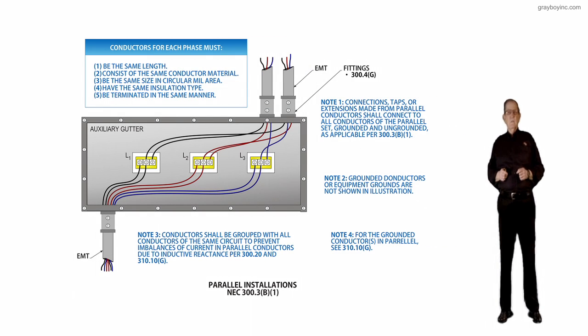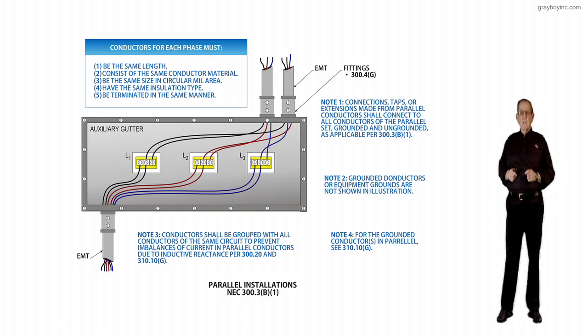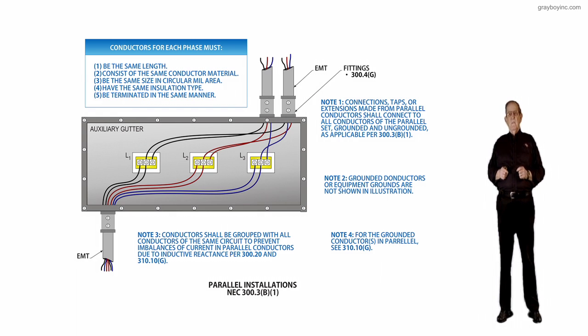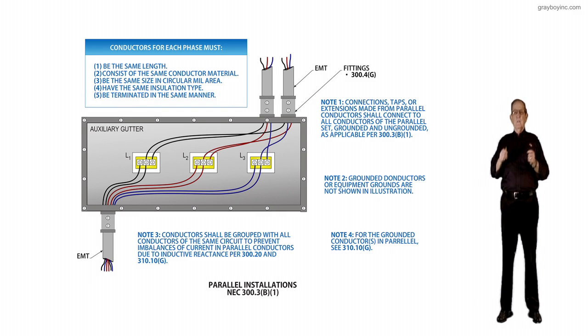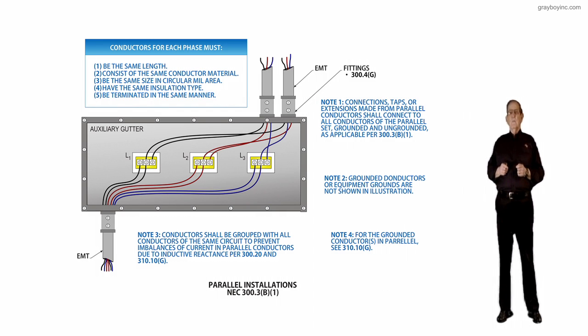This new section deals with parallel installations in accordance with NEC 300.3B1. The purpose of change was a new sentence that has been added to require that connections for a parallel set of conductors include all of the conductors of the set, and not just one of the conductors in parallel, as has been done in the past.